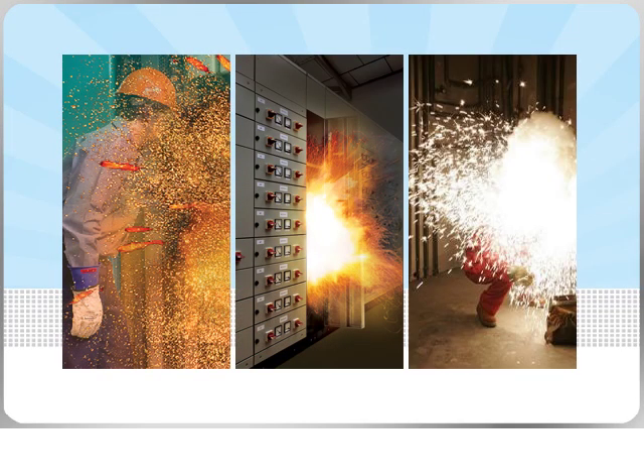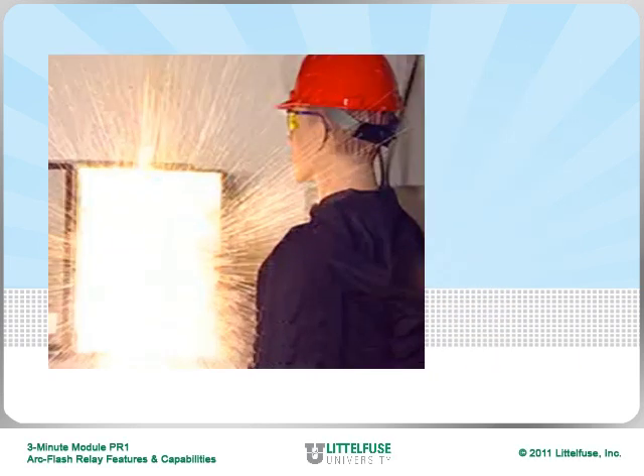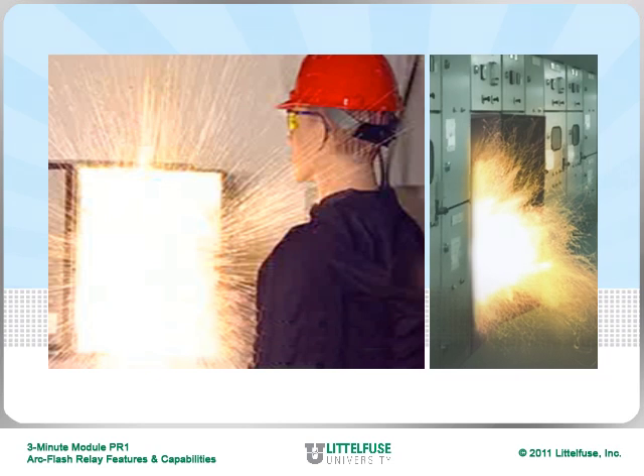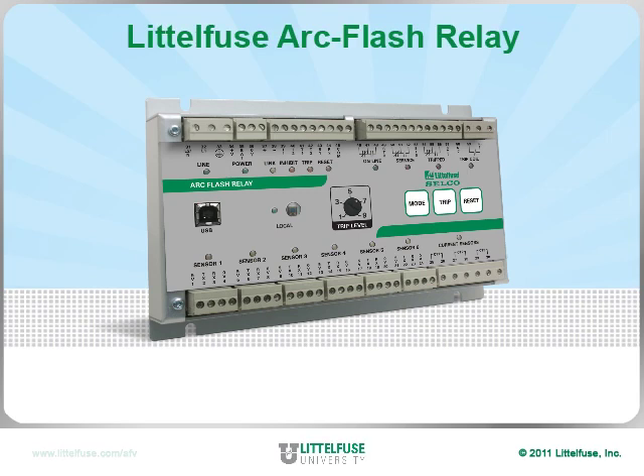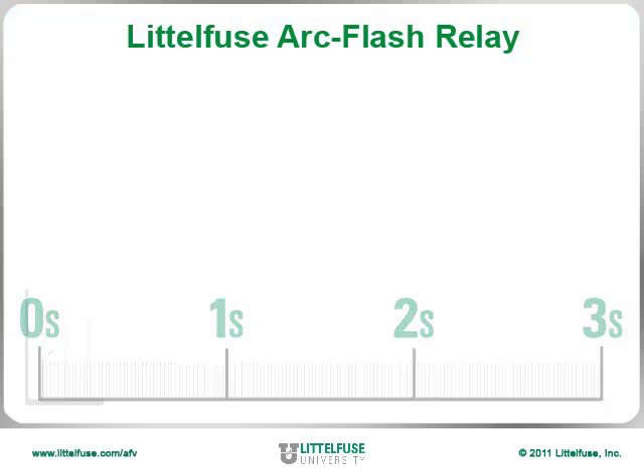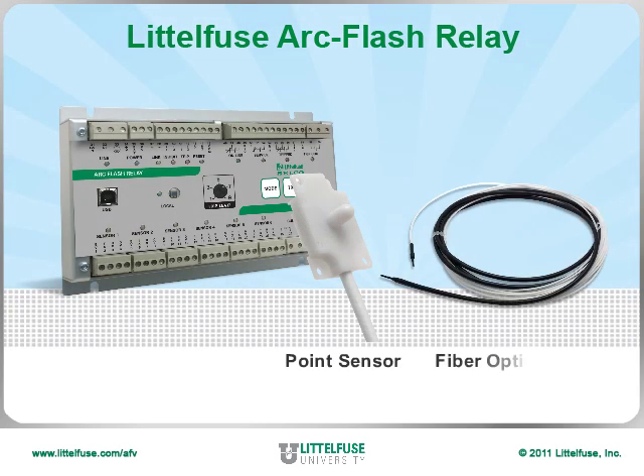Arc flash and electrical hazard risks should not be ignored in your facility. Arc flash protection should be used when working on energized equipment, and Littelfuse has a solution to provide this protection. The arc flash relay quickly detects arc flash events and sends a trip signal to a circuit breaker in less than one millisecond. Light sensors detect the initial spark.